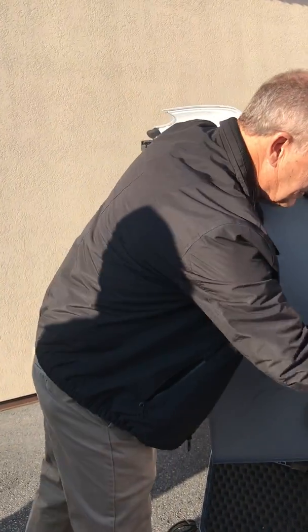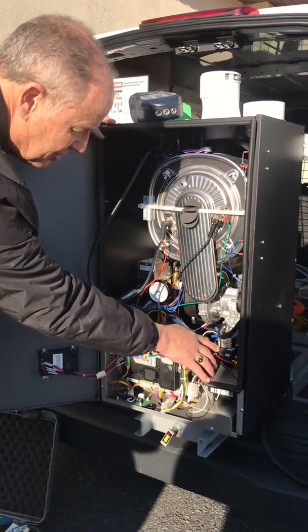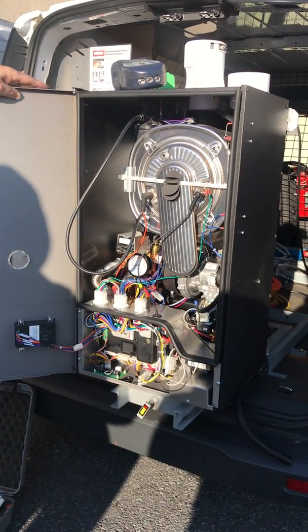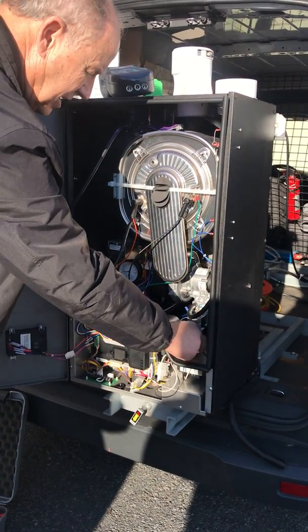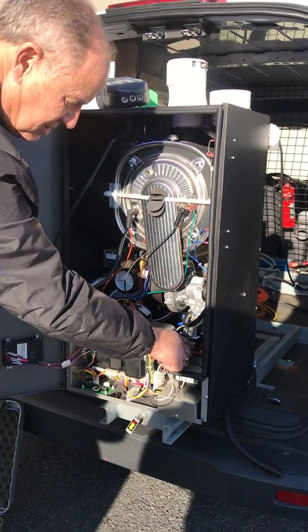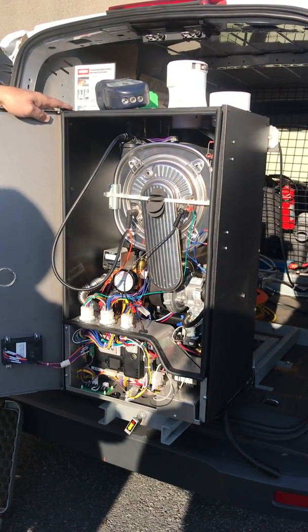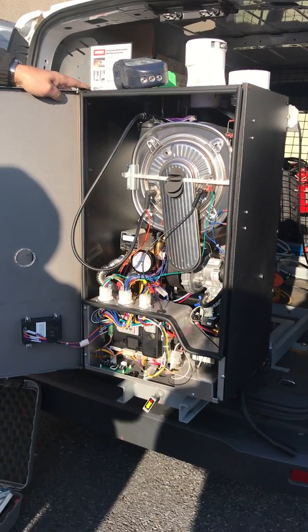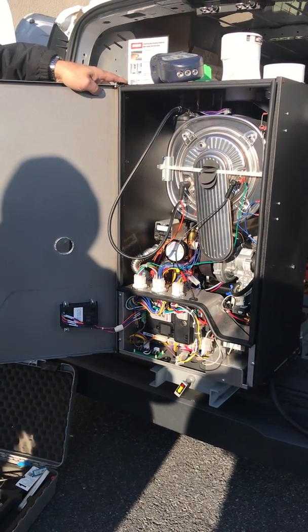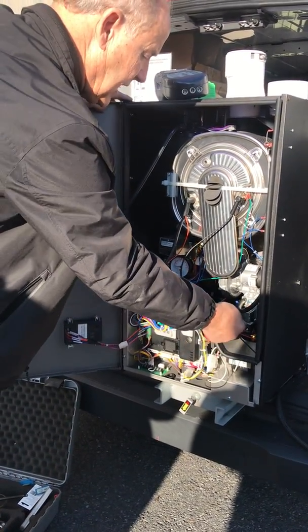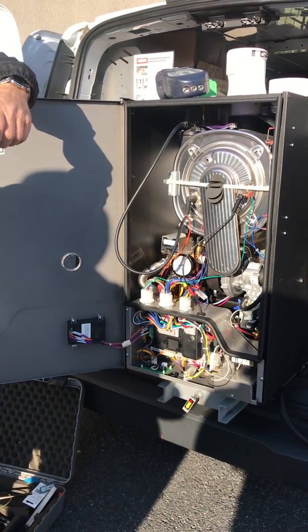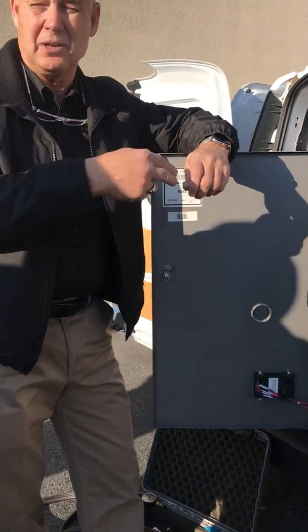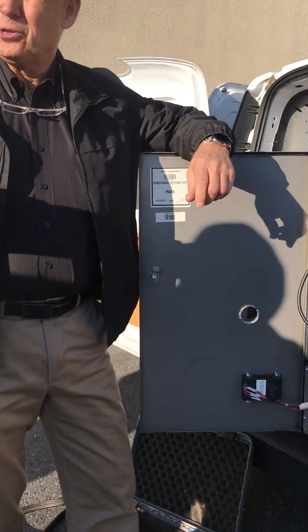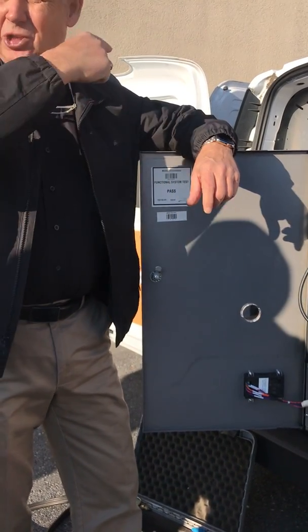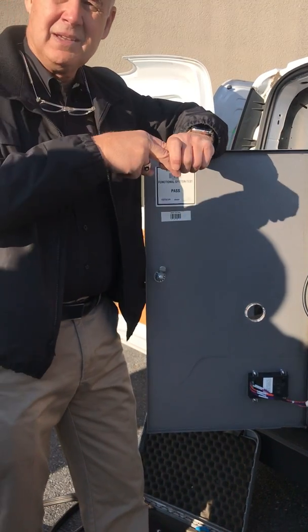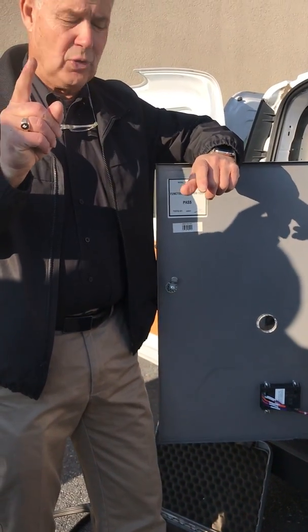Now, here's another thing. Down here on the gas valve, there's a little thing called a rectifier. And my gas plugs right into here. Somebody disconnected the gas, but it plugs in. It's usually a blue and yellow wire. If you ever have a problem and you don't know whether the gas valve's working, we can unplug the wire from the gas valve. And when it goes to light, we can actually check with our voltmeter for 24 volts. When it goes through and you get direct ignition, I'll show you upstairs, at that time check for 24 volts. We have 24 volts there.